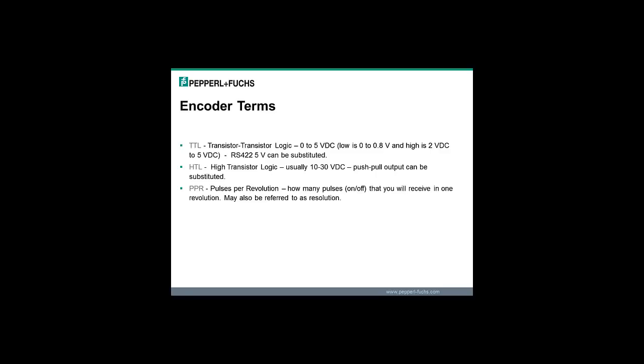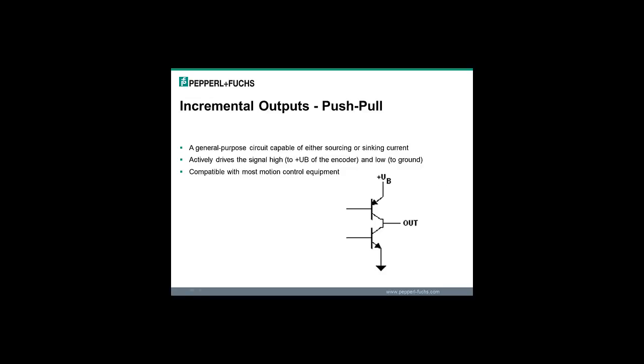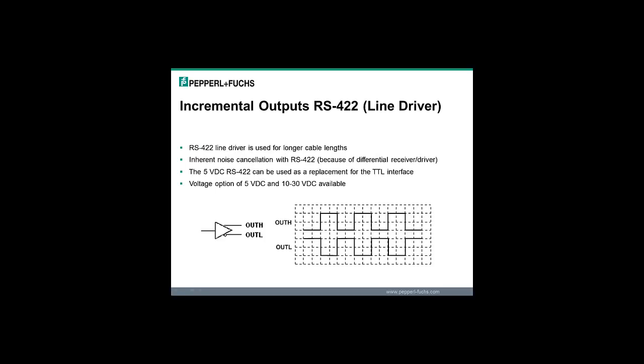Pulses per revolution or PPR is how many pulses are on the incremental code disk. If you know the PPR of an incremental encoder, it can help you determine the resolution. The push-pull output can be wired for sourcing or sinking output, compatible with most PLC and counter 24 volt DC inputs. The RS422 line driver output is used for longer cable runs and has inherent noise cancellation because of differential driver and receiver.